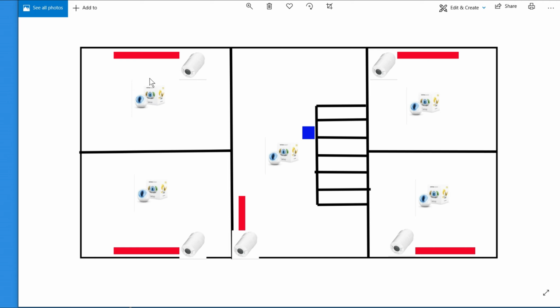That's where the multi-sensor comes in, because just before it sends a signal across to the boiler and the valve, it actually checks, is this room actually occupied? If it's occupied, it will then do everything it needs to do to warm up the room. But if the room is empty, what's the point of heating up an empty room? So we've gone one step further. I have set a differential, a time window of 15 minutes.